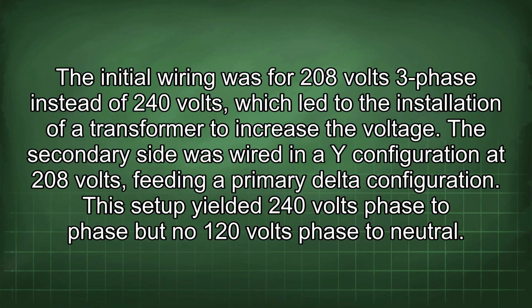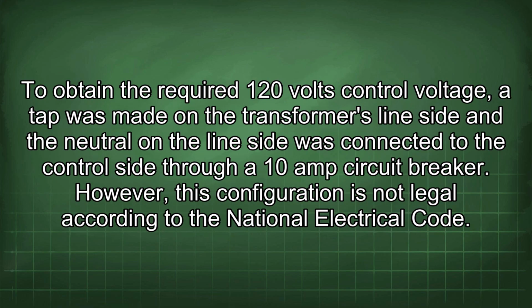The secondary side was wired in a Y configuration at 208 volts, feeding a primary delta configuration. This setup yielded 240 volts phase to phase but no 120 volts phase to neutral. To obtain the required 120 volts control voltage, a tap was made on the transformer's line side and the neutral on the line side was connected to the control side through a 10-amp circuit breaker. However, this configuration is not legal according to the National Electrical Code.